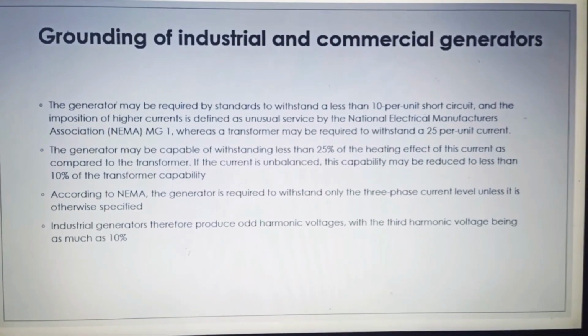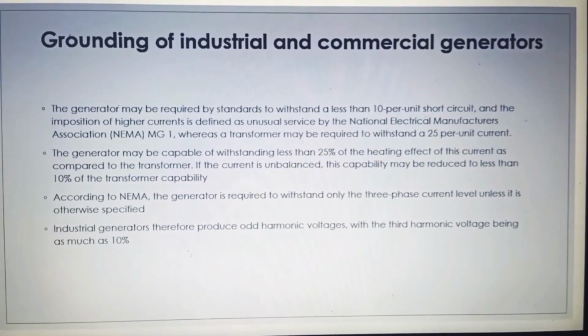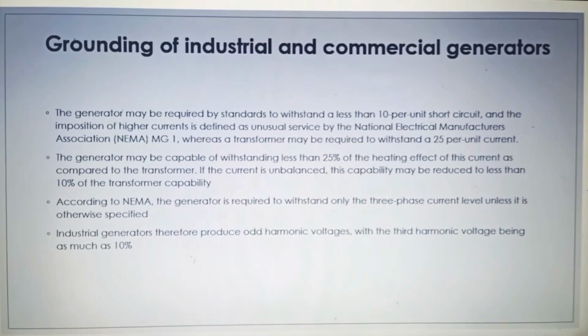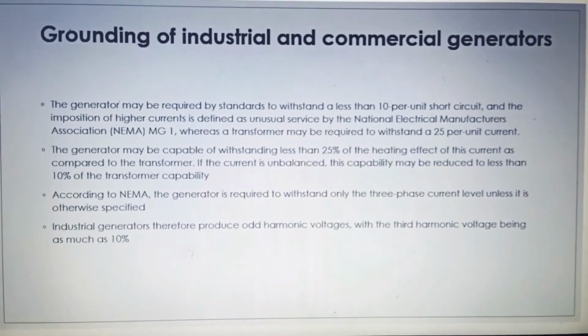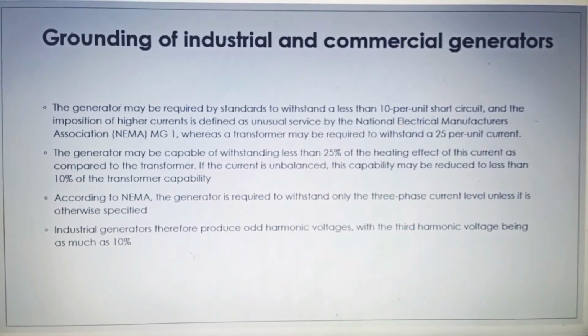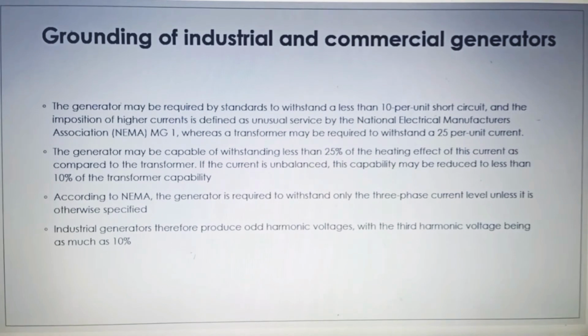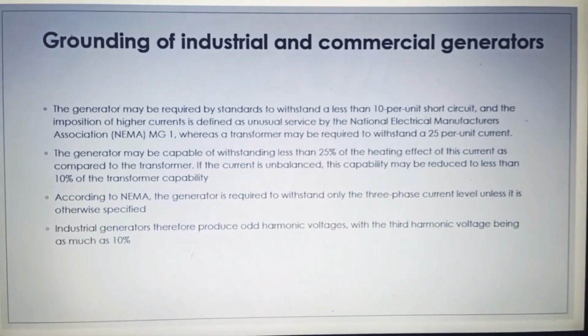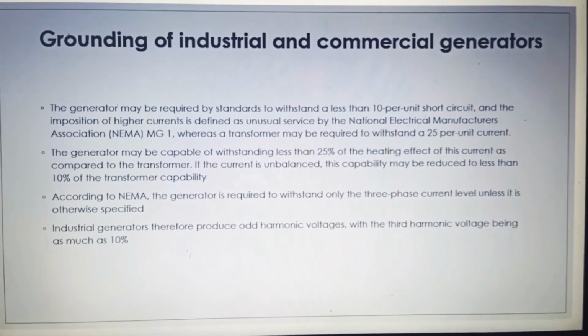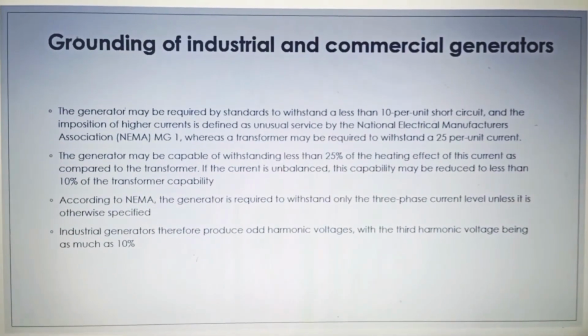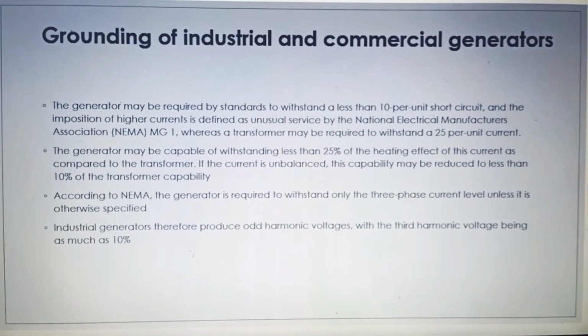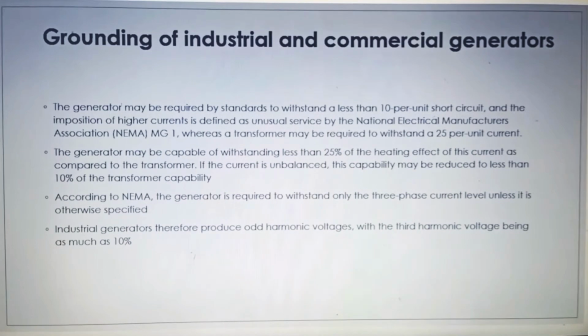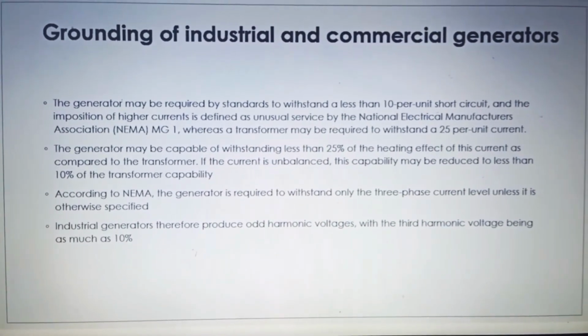The third harmonic voltages produced in the generator winding are in phase and additive. This would be the cause of harmonic current circulating within a delta-connected winding. The circulating current would create additional heating in the generator, thereby reducing some of its thermal capacity. Generators that operate in the delta connection allow for this in their design.